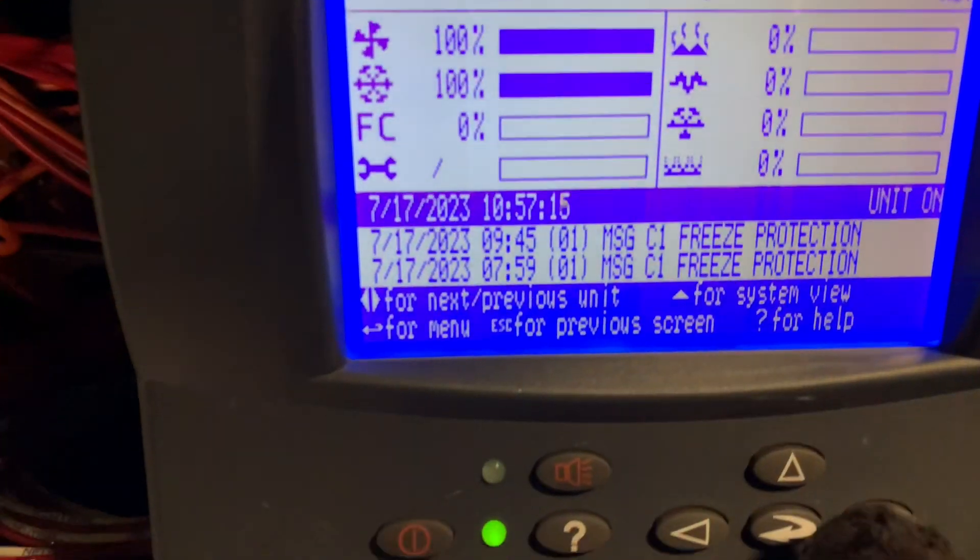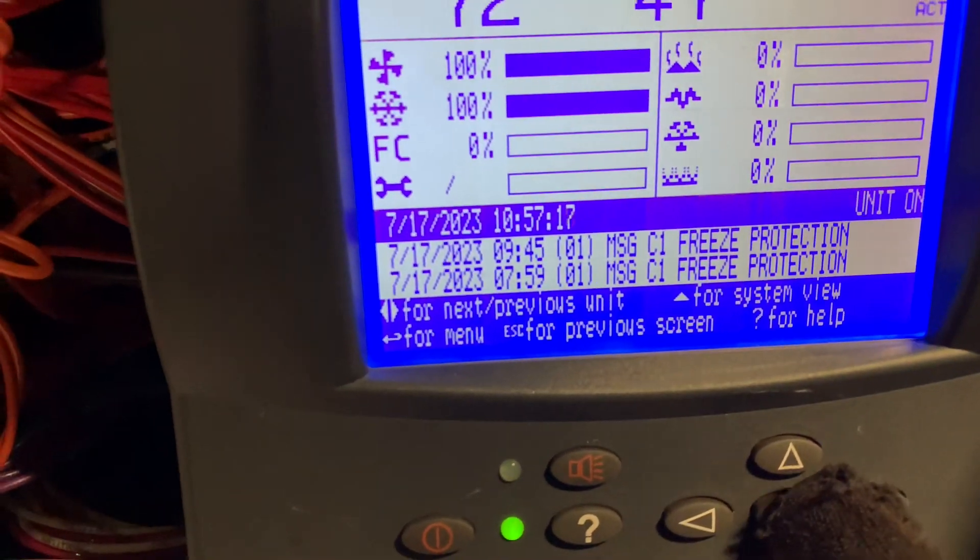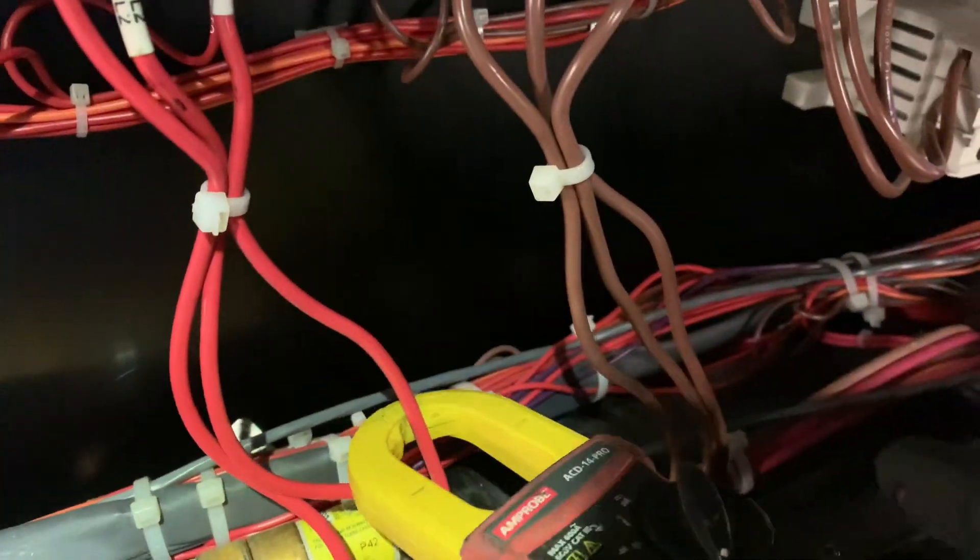So the reason why you get this alarm or warning is simply because the system is telling you that it's low on refrigerant.